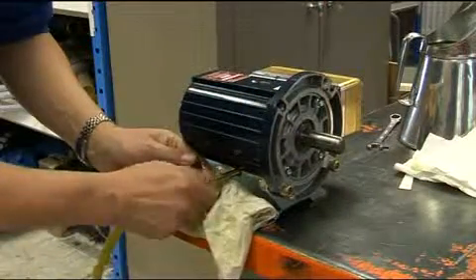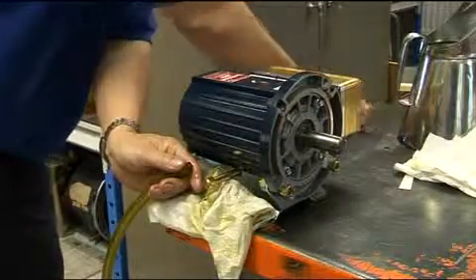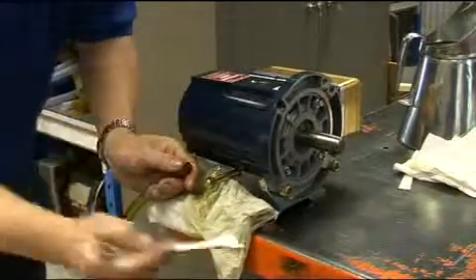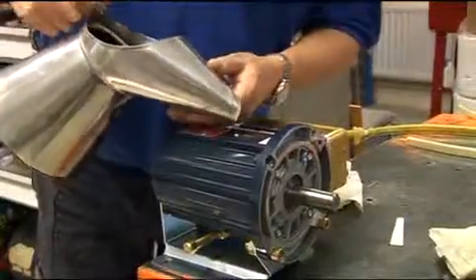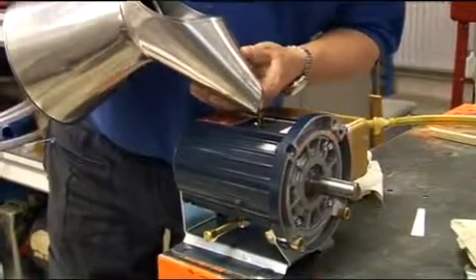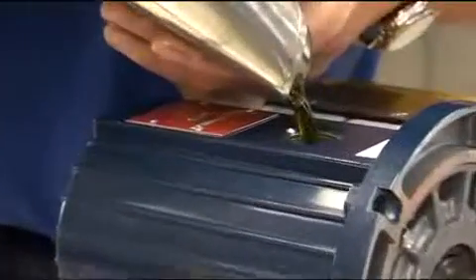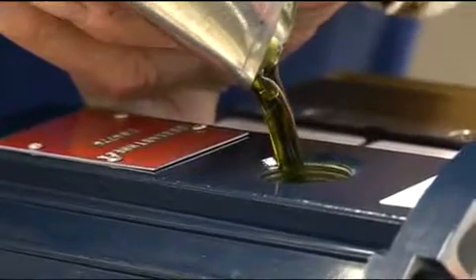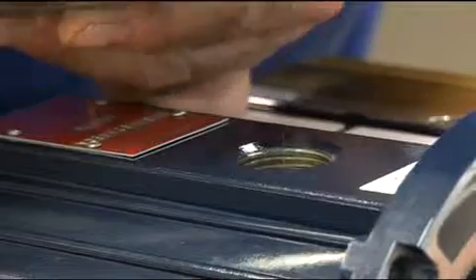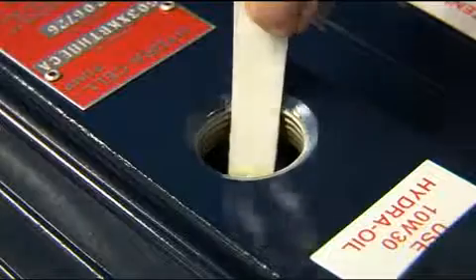Replace the drain plug cap and refill with the appropriate Hydra-Oil to the correct level. The level should be 6mm from the top of the fill port.